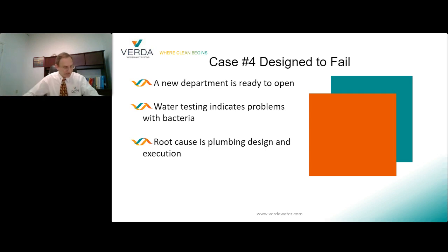Check. An initial water test for bacteria, HPC, showed a reading of 11 CFUs per milliliter; the requirement is less than 10, so they were right on that threshold. The next time they checked, a few weeks later, it was now 20. So they started checking more sampling locations, and point-of-use samples ranged anywhere from less than 1 to over 1,400 CFUs. Nine months later, they were still getting HPC readings ranging from 2 to 60 CFUs.